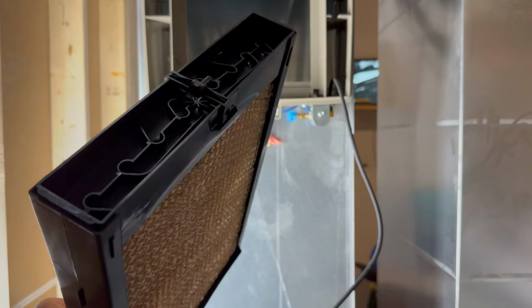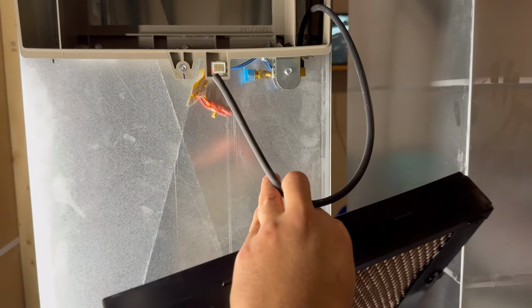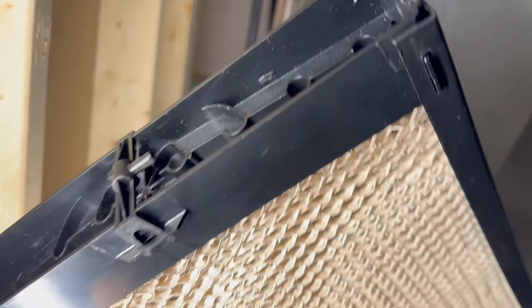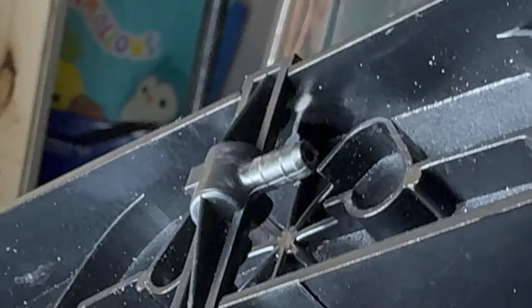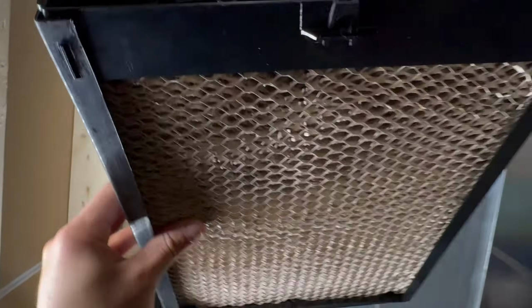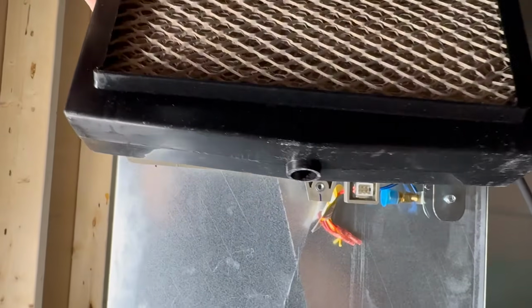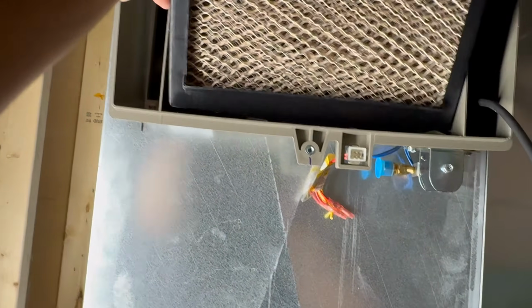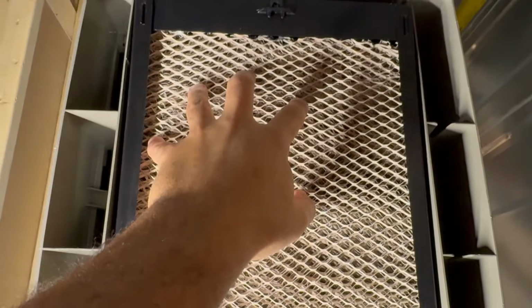Now going to reinstall the humidifier pad. So just make sure you take that water line and you're going to attach it at the top here. See where that little nipple is? Right there. Reattach it, and then you're going to put it in.